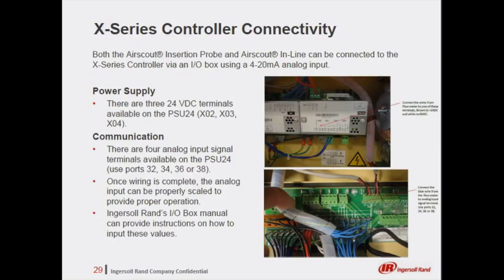Both the Airscout insertion probe and inline flow meters can be connected to the X series controller via an I/O box using a 4 to 20 milliamp analog input. As seen in the internal I/O box pictures here, there are two parts to the connection, which are the power supply wires and the communication wires. There are three 24-volt DC terminals available on the PSU-24 and 4 analog input signals available. Once the wiring is complete, the analog input can be properly scaled to provide the proper operation. The I/O box can provide instructions on how to input these values.